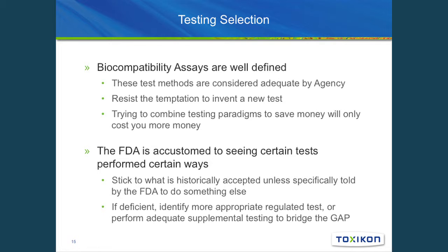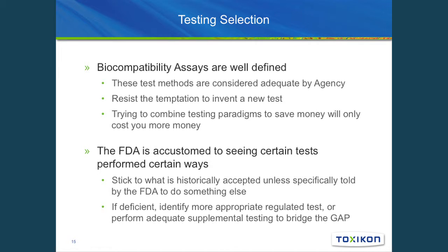And really, if you've identified a deficiency, my background's in biomedical engineering, we always find why the tests don't really assess my product the right way, the way I'm going to use it for my patient. If you've identified some deficiencies, there even is some language in the 10993 that says if your product is not properly assessed for its safety, not efficacy, then go back and see what additional testing you can do.